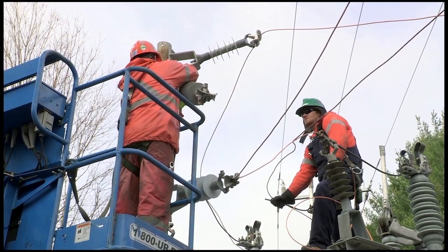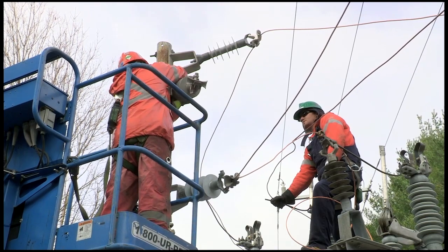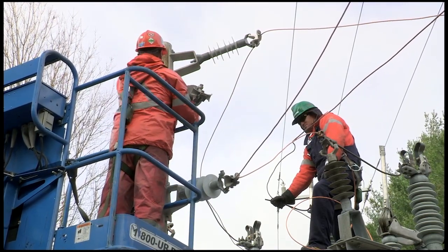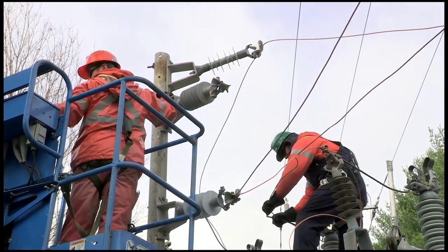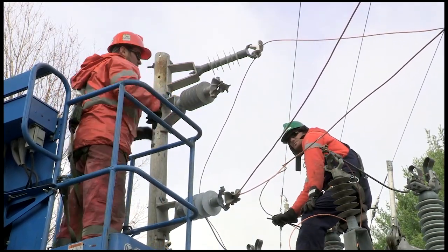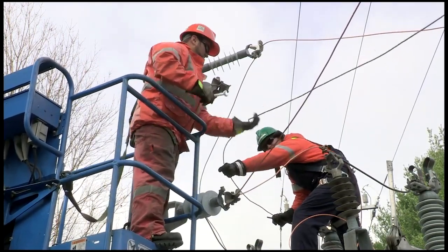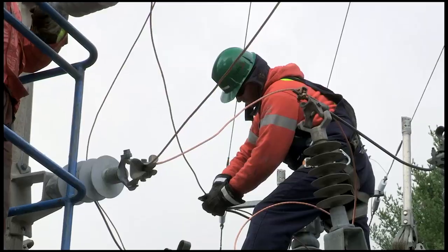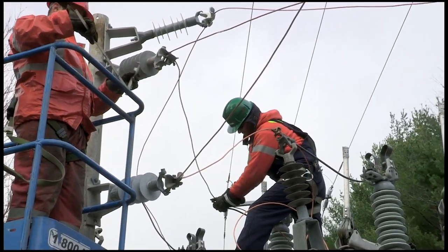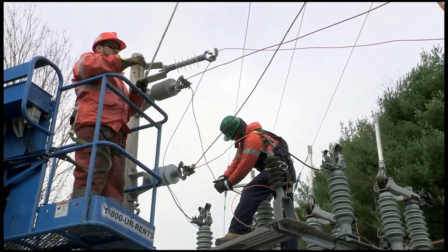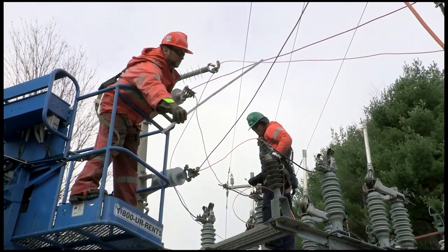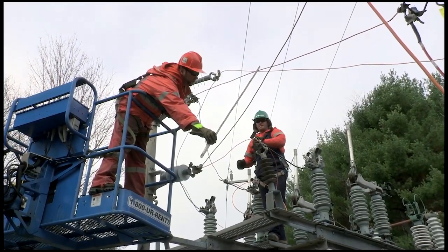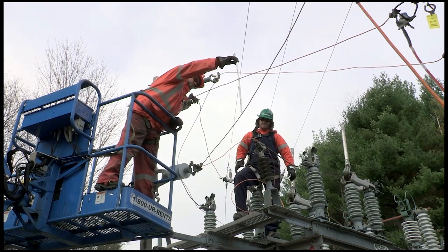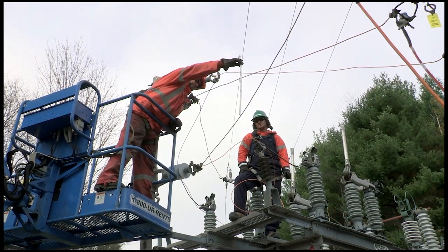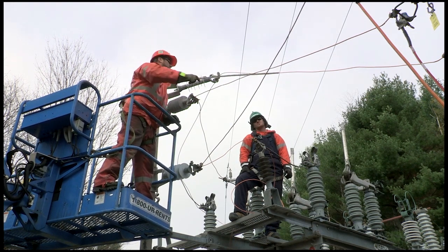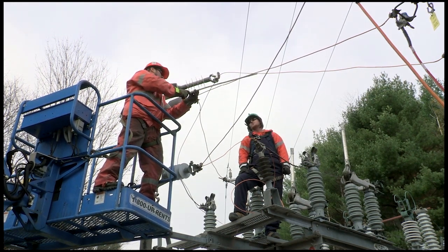This requires one person to support the conductor and one person to move the insulator. Reclamp the conductor to the insulator and connect it to the switch connection point. Then check the clearances again. After you have confirmed that the phasing arrangement and clearances are correct, cut off the conductor tails at the switch end. Alternative methods for obtaining the proper electrical clearances may include lengthening devices to get the conductor further out.